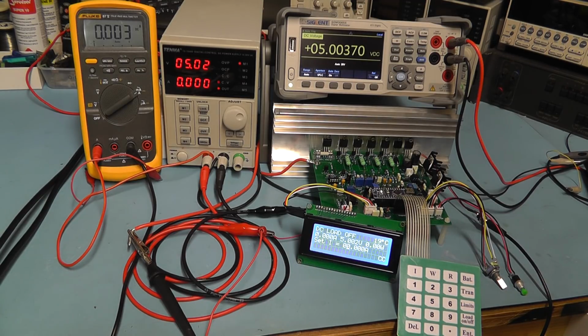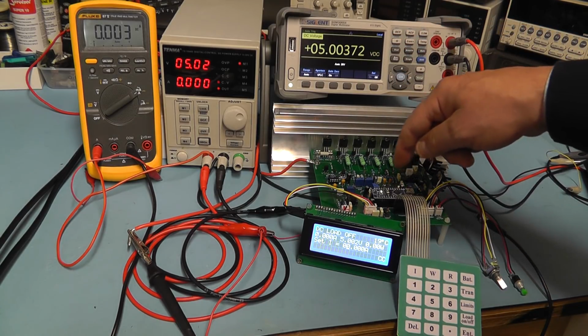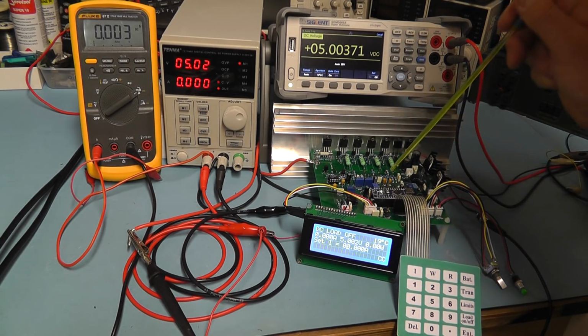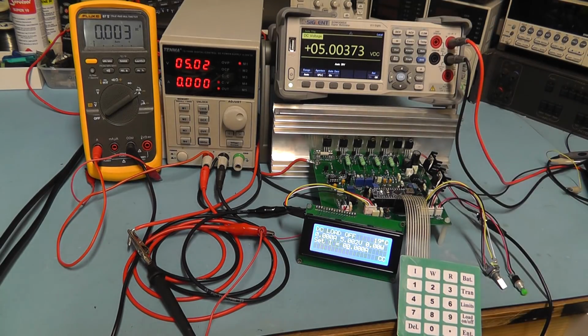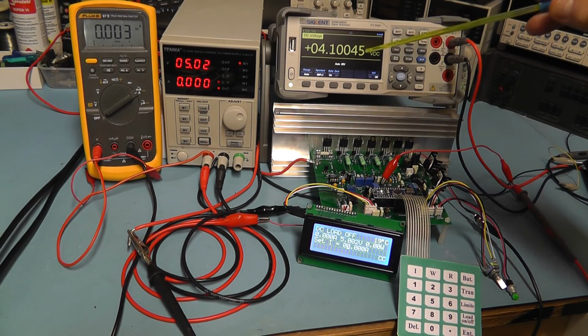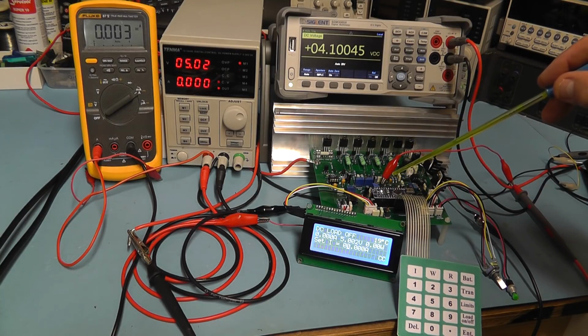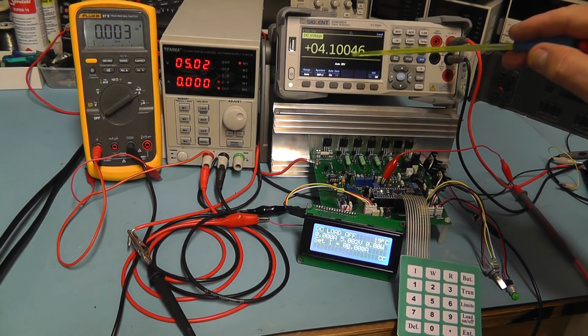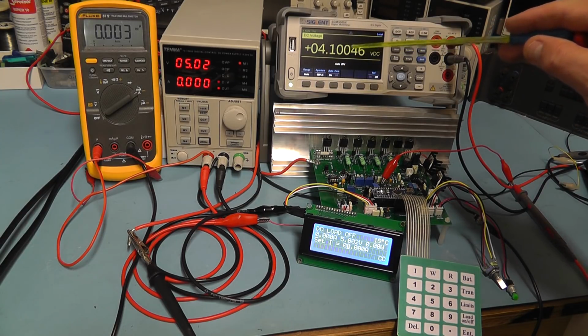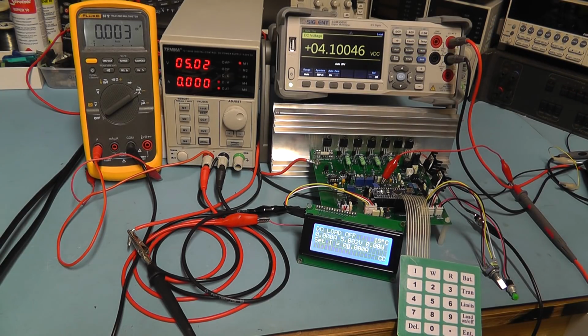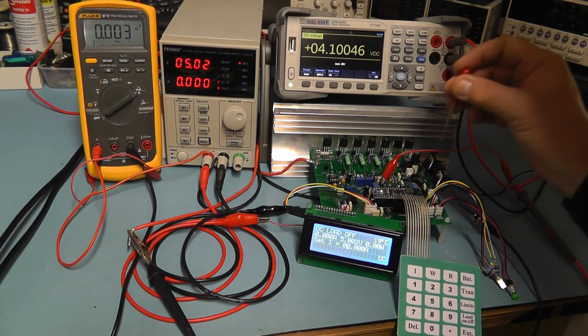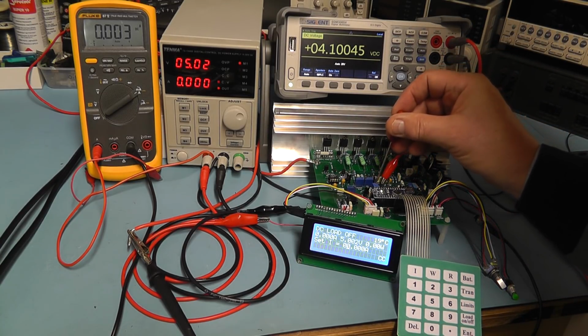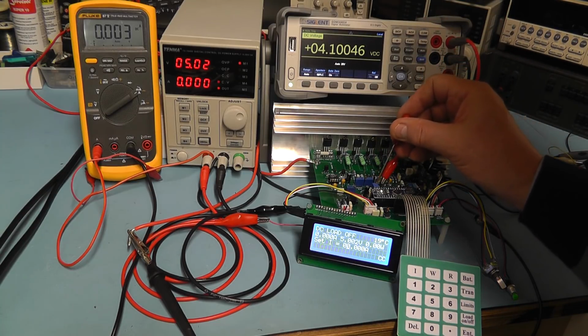The next thing we're going to do is set the voltage reference on the board. That's the 4.096 volts, and to do that I'm going to connect the meter here to that reference pin which we have here on the board. So let me just do that. Right, we now have the meter connected to the 4.096 volt reference pin, and we're just monitoring that. You can see at the moment it's reading 4.1004. So I'm going to adjust that with the reference preset, which is just there, and get 4.096 volts on the meter.